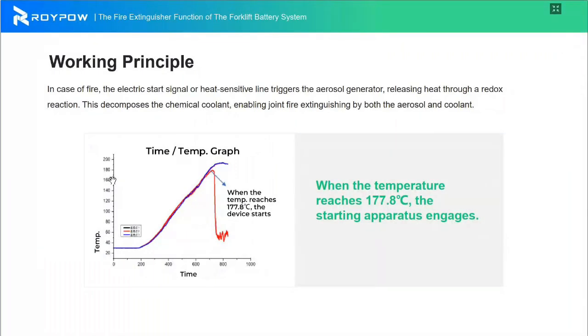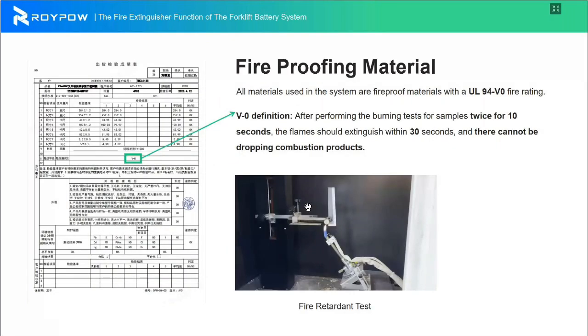In case of fire, the electric start signal or heat sensitive line triggers the aerosol generator, releasing heat through a redox reaction. This decomposes the chemical coolant, enabling joint fire extinguishing by both the aerosol and the coolant. All material used in the system is fireproof, with a UL94-V0 fire rating, which is the highest level.